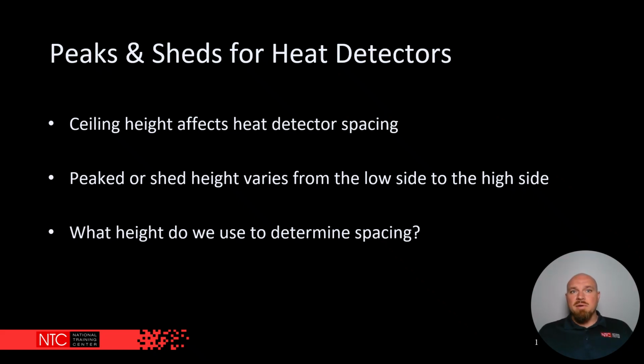Ceiling heights are going to have an effect on your heat detectors. Let's take 2 minutes to talk about peaked or shed ceilings and how to figure out the spacing of your heats. So, ceiling heights play a factor into the necessity for adjustments with your heat detectors. If it's greater than 10 feet, you're going to have to do an adjustment.